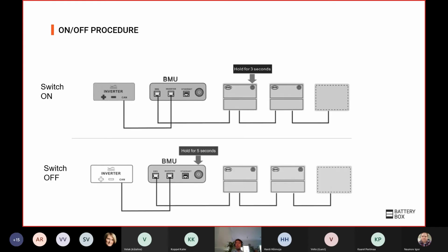You need to be mindful of the switch on, switch off procedure. Same as with the high voltage unit, make sure the inverter is off first, then click on one of the batteries. This will switch on all the batteries, and it will switch on the BMU. Do the commissioning, and when you finish the commissioning, you can switch on the inverter. The switch off procedure is the other way around. First switch off the inverter, and then press the BMU for 5 seconds, and this will switch off all the units.